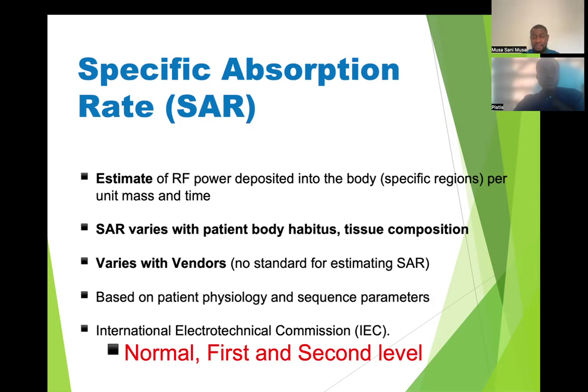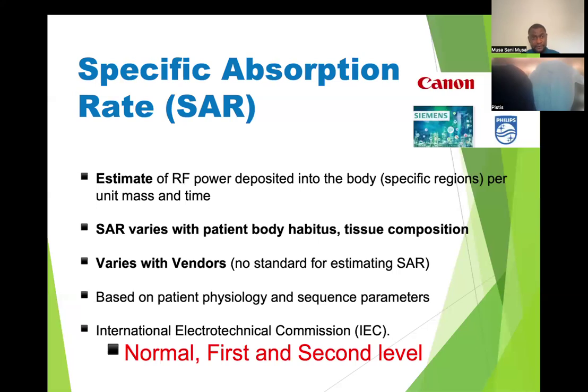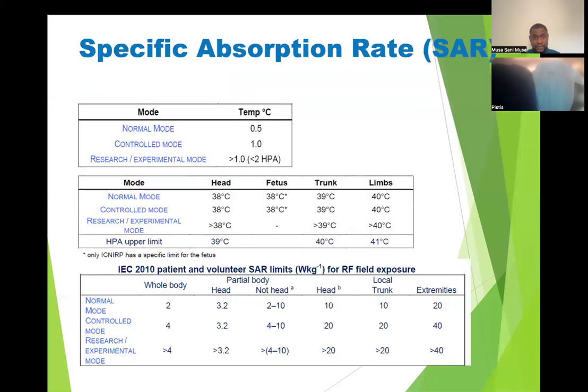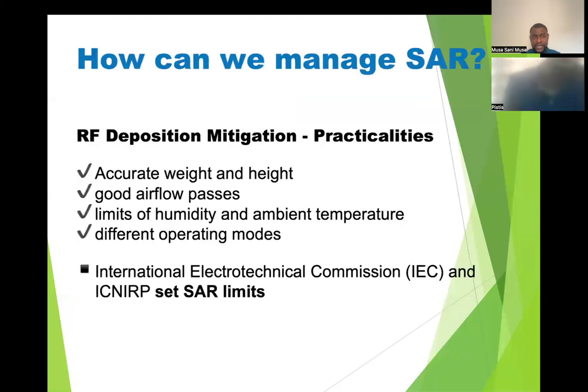As a result, they've got implants which can easily be overheated, and we all know what's going to happen. RF burns is number one, the likely repercussion of scanning a patient at usually first level or second level. So we should try and stick to our normal level if possible. These are just some information about the specific absorption rate. So how can we manage SAR now? Like I said, taking accurate weight and height of the patient, different operating modes, just making sure that we stick to the normal SAR mode if possible.